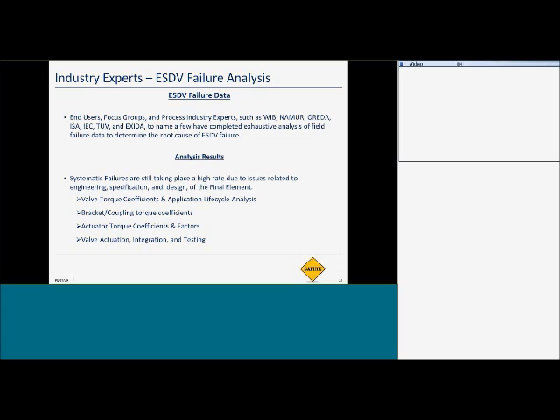And finally, in the actuation integration, assembly, and testing, they found issues, whether it was undersized tubing, solenoid valves not sized sufficiently, all kinds of different systematic issues that develop around the integration and assembly of the package. So these were four major areas when it comes to the final element that were identified as major red flags and areas of concern.